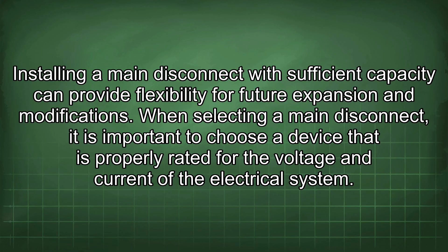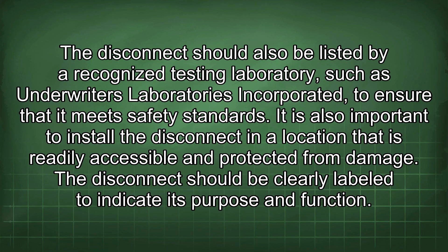When selecting a main disconnect, it is important to choose a device that is properly rated for the voltage and current of the electrical system. The disconnect should also be listed by a recognized testing laboratory, such as Underwriters Laboratories Incorporated, to ensure that it meets safety standards. It is also important to install the disconnect in a location that is readily accessible and protected from damage. The disconnect should be clearly labeled to indicate its purpose and function.